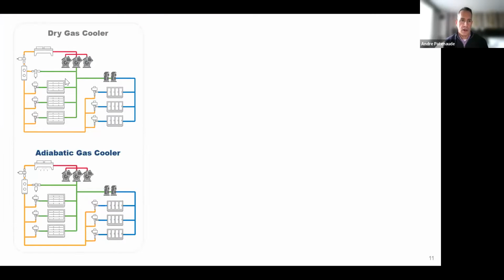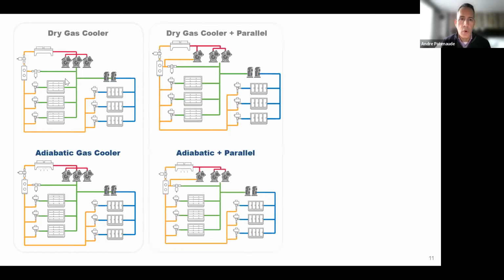If you're not that familiar with the architecture, I built some stick diagrams. If we start on the top left corner, we're looking at a standard booster system. Now, I didn't put the oil system in there. I didn't put dump solenoid valves or filter dryers, just the line sets basically, so it's easier to follow. But you've got your dry gas cooler on the top, and then if you go down to the bottom left, I've got the little spray nozzles underneath the gas cooler. That's my indication that it's an adiabatic. So that's one strategy that's important to compare against one another because it's very popular in the US right now. It is the most popular high ambient strategy that I would estimate.